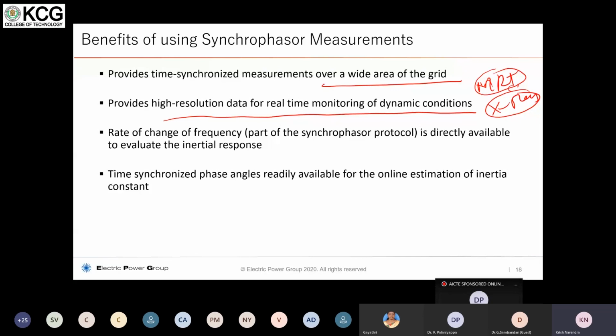Okay, so it does not suppress the events, the significant events and phenomena that happen in power systems, whereas with SCADA data it is possible that we will miss a lot of important functionalities such as oscillations and other things. It's very good for steady state conditions, but not for dynamic operations. For dynamic operations, it's very important to look at synchrophasor measurement.